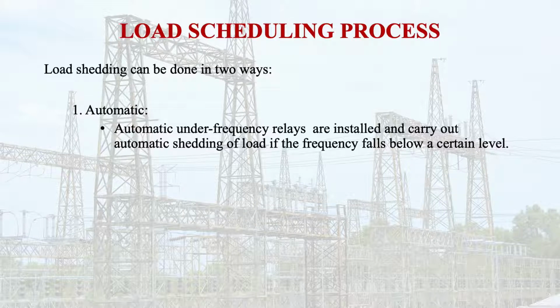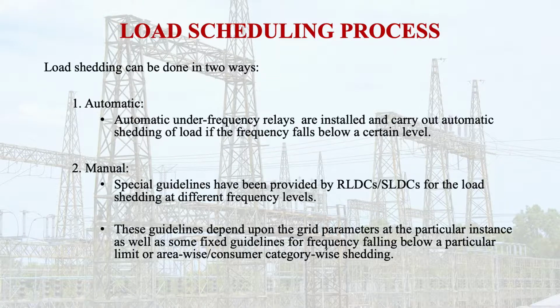These are installed, and these relays carry out automatic shedding of the load if the frequency falls below a certain level. And for manual load shedding, special guidelines have been provided by the regional load dispatch center and state load dispatch centers for load shedding at different frequency levels. These guidelines depend upon the grid parameters at a particular instance, as well as some fixed guidelines for frequency falling below a particular limit, or area-wise or consumer category-wise shedding is also there.